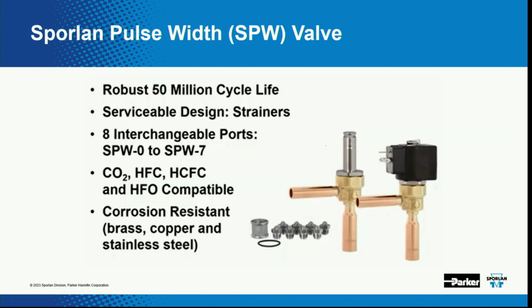Now, this next slide is showing our pulse width valve, and we call it an SPW, Sporlan pulse width, and that will kill two birds with one stone because this is actually modulating the valve to expand the refrigerant, so it's our expansion device, and at the same time, it's also our liquid line solenoid because if we do lose power, that valve will go closed and you'll stop the refrigerant flow. So it's killing two birds with one stone. It's actually killing over 3,000 birds with one stone because that single valve replaces about north of 3,000 SKUs, Sporlan specific item numbers that we have, because it's so universal. It's got 8 different interchangeable ports or cartridges that you can put into it, depending on what your tonnage is.